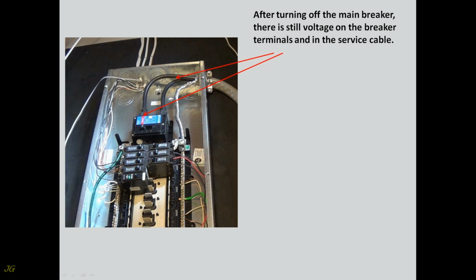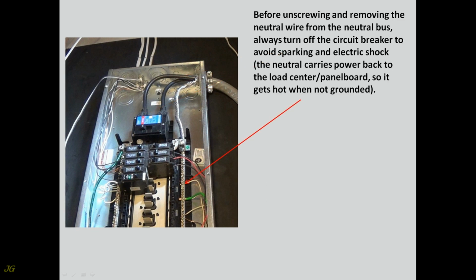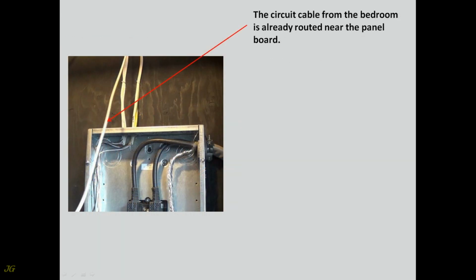After turning off the main breaker, there is still voltage on the breaker terminals and in the service cable. Before unscrewing and removing the neutral wire from the neutral bus, always turn off the circuit breaker to avoid sparking and electric shock. The neutral carries power back to the load center, panel board, so it gets hot when not grounded. The circuit cable from the bedroom is already routed near the panel board.